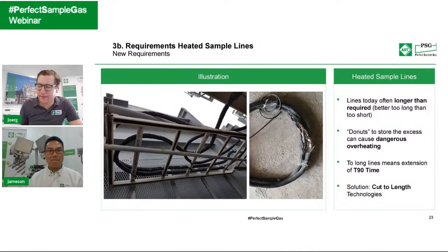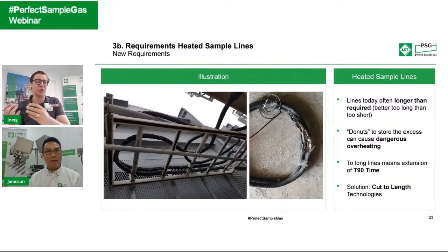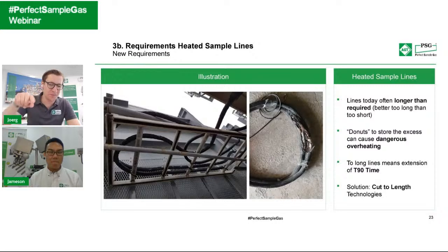Yeah, that's true. And the quick fix is really also to explain what you can do. Therefore, I like your idea, Jameson, to give some general hints for the installation, what you have to take care of, right? So let's pretend you have not chosen the PSG model, which you can cut to length. So you decided to go for the fixed resistance heated sample lines, which you cannot cut to length. But still, if you have a longer length, make sure that there's enough space between the heated lines so that they are not getting too close together. Because as you can see in the picture, this is a real threat and a real problem which can occur there. You accumulate the heat, and then the materials can really start even to burn.